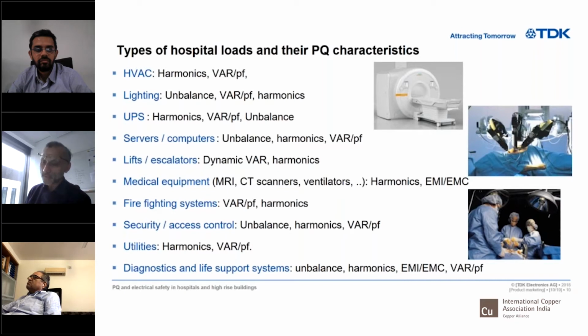And today's lighting, unfortunately, is no longer the Edison's incandescent bulb. Either you have CFLs or you have LED SMPS drivers, which means the power factor could be as low as 0.4 and as much as 70% THD. Then you have UPS. Of course, hospitals need UPS. You will not start an open heart surgery without a backup supply. But UPS do generate harmonics.